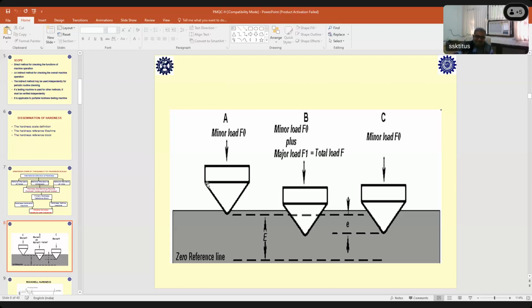Now at this stage you can just visualize a conical indenter being used in the case of Rockwell hardness. How is this conical indenter used to make a penetration? We need to apply a force. So what is the force required to make the indentation on a sample? This conical indenter is plunged into the sample by applying a force of 10 kg at the initial stage. So apply a force of 10 kg, which we call F naught. Then you make an initial indentation, just a penetration on the sample.